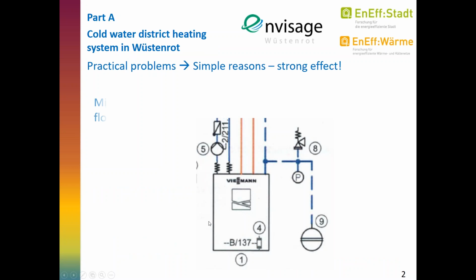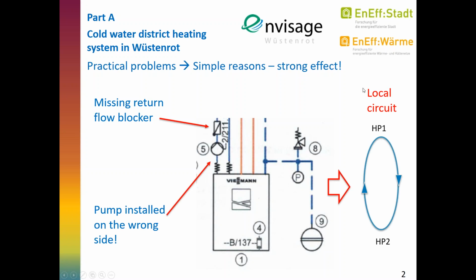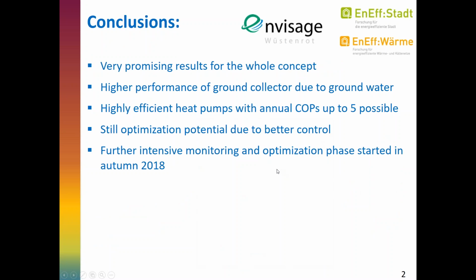But here's the interesting part: since this was at the very end of the network, there was a kind of circulation between two heat pumps at the end, with nearly no geothermal source available providing heat — only this short network part. This resulted in the temperature dropping quite significantly and fast, down to -9 degrees, and then we stopped the operation of the system. This shows that problems can happen even with good maintenance and everything done properly. Shit happens also in these systems, but it was quite interesting and can of course be avoided in the future.